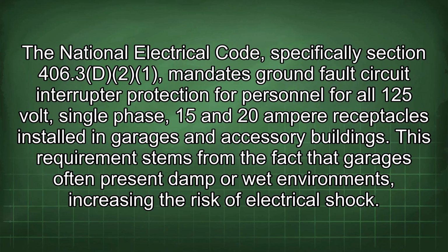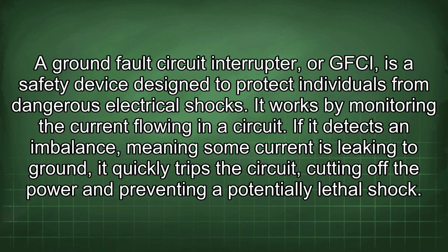The National Electrical Code, specifically Section 406.3(D)(2), mandates ground fault circuit interrupter protection for personnel for all 125-volt single-phase, 15 and 20 ampere receptacles installed in garages and accessory buildings. This requirement stems from the fact that garages often present damp or wet environments, increasing the risk of electrical shock.